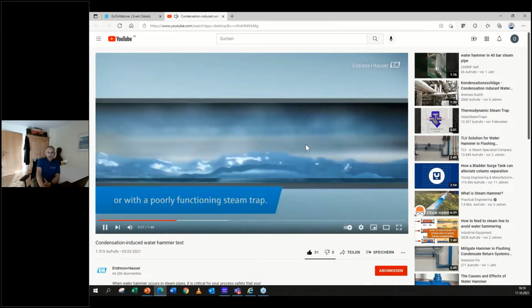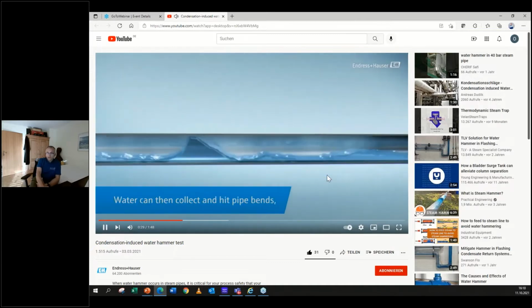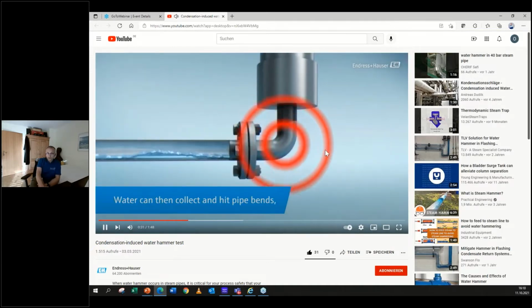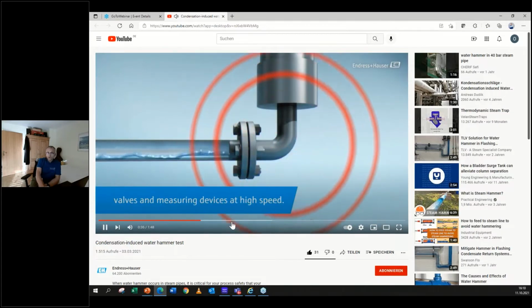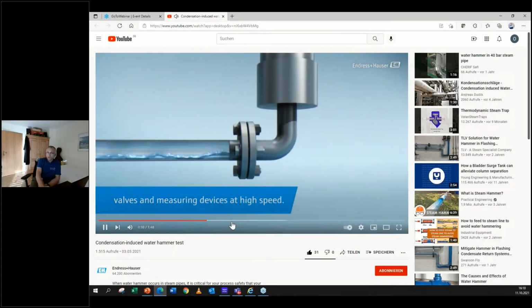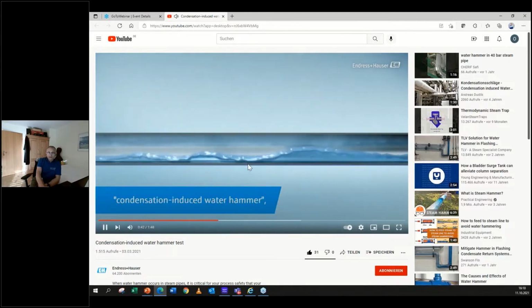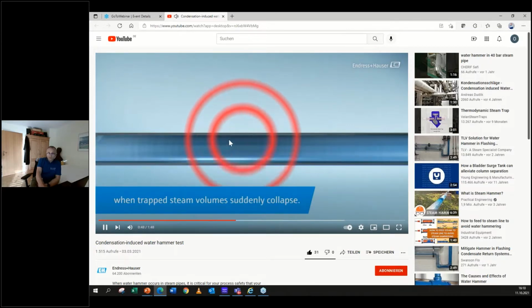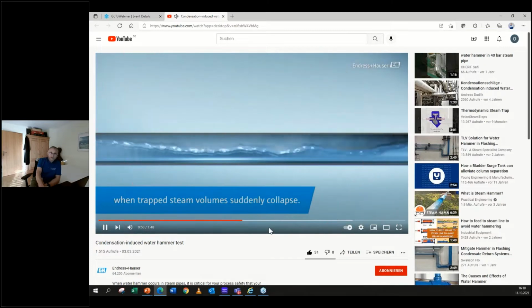First, you see how a water hammer looks like. Here we see some slug flow water hammer. This is not what we're talking about here. We're talking about condensation-induced water hammer in this test. So you have water, and in that water, you have a bubble of steam, and that then collapses, creating vacuum. This is what you've seen right now.